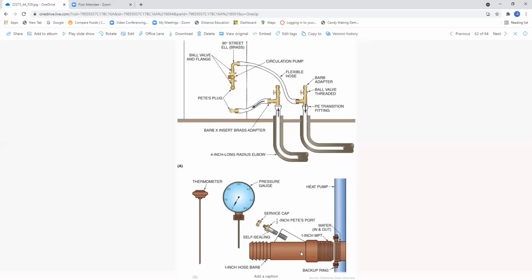Notice that you've got a 1-inch hose barb, backup ring, and you have a Pete's port where you have the ability to read the pressure. It has a self-sealing part so the water can't blow out. And of course, you have the ability to measure the temperature. And here, these are your access points on this ground loop heat pump system, the circulation pump. So you have the ability to check the flow rates by these devices, which are hooked up when the system is put in and commissioned. If you don't have these Pete's plugs, as an example, you're going to have a lot of trouble troubleshooting this system, and you're going to have to add these components later on.